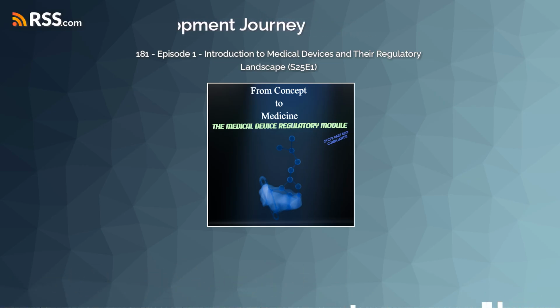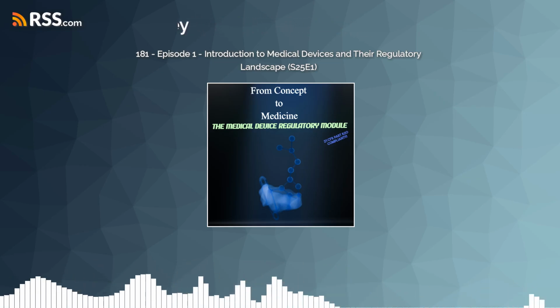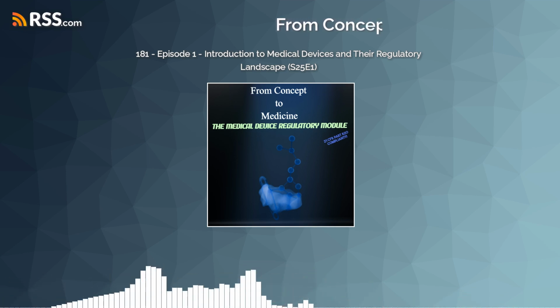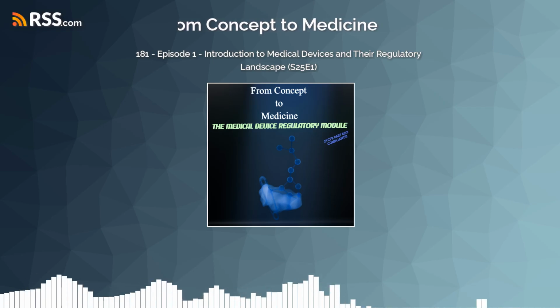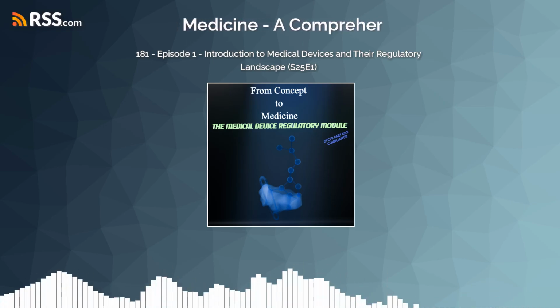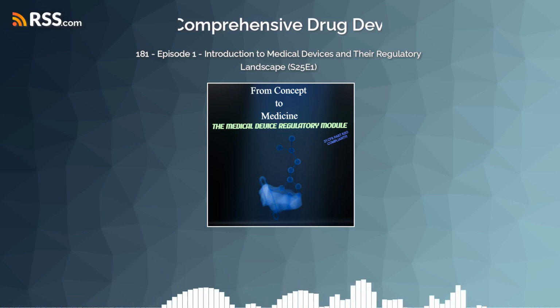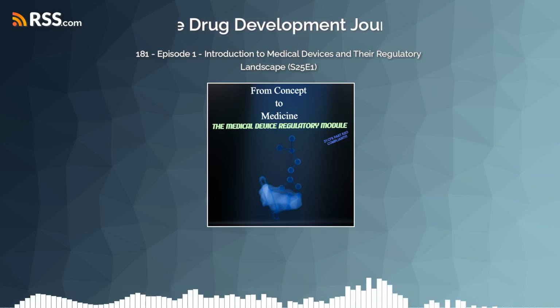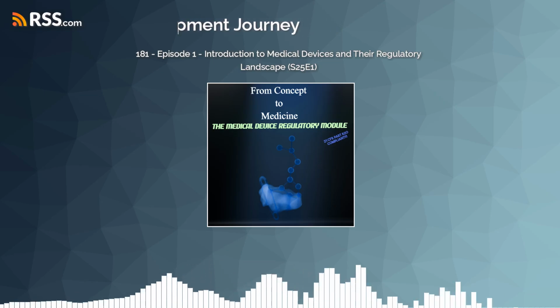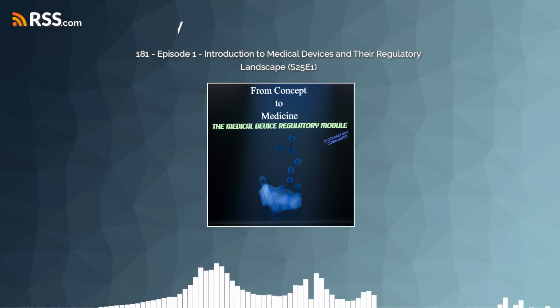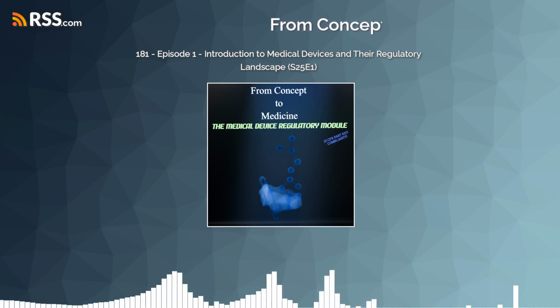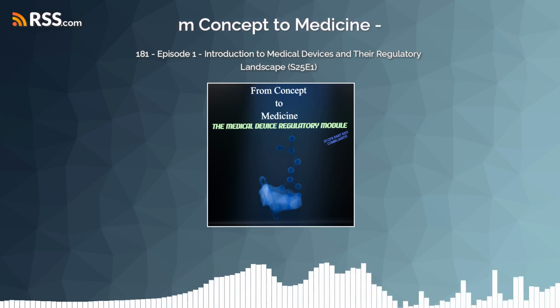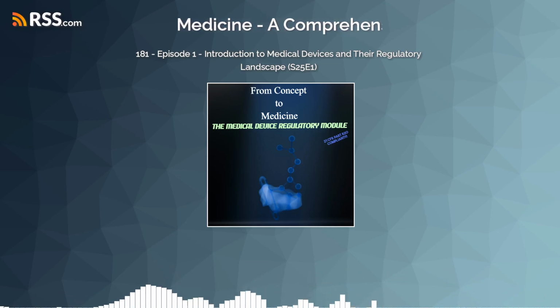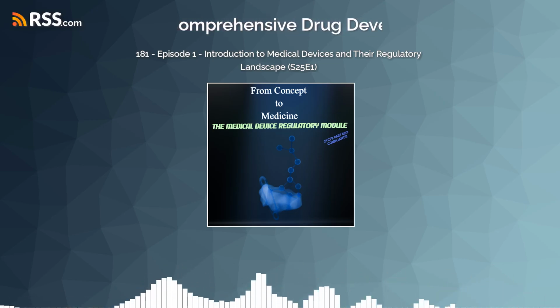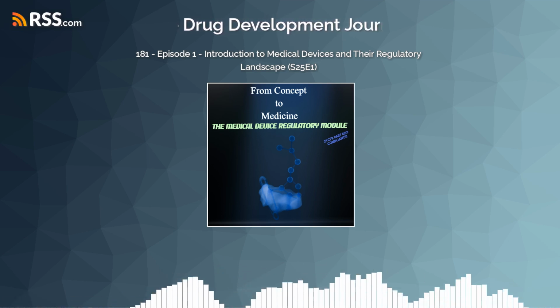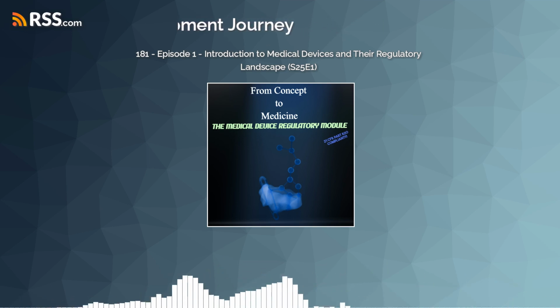EU MDR. Okay, so how does that EU system compare to the FDA system we've been discussing? What are some of the key differences, maybe philosophical or practical, that manufacturers need to grasp if they're aiming for both U.S. and EU markets? Well, one of the most fundamental differences is the regulatory body itself, or rather the structure. The EU uses what are called notified bodies. Notified body. Yes, these are independent, third-party organizations accredited by national competent authorities. They are the ones who actually audit the manufacturer's quality management system, review the technical documentation for most devices, and assess conformity with the MDR requirements. If everything checks out, they issue the CE mark certificate.